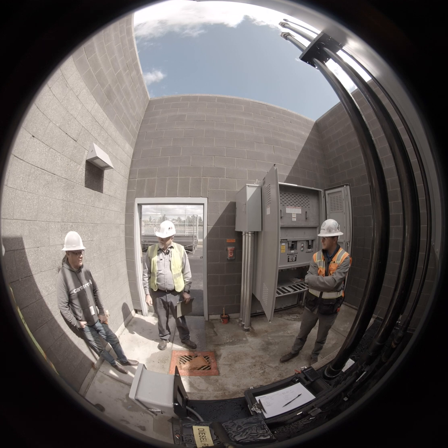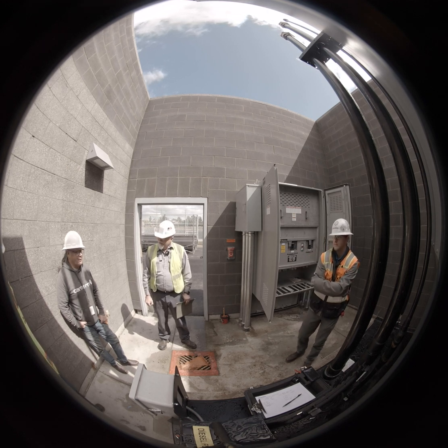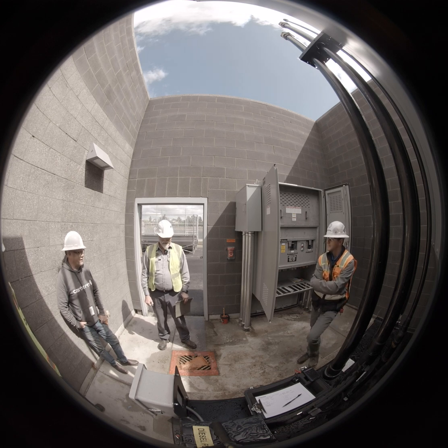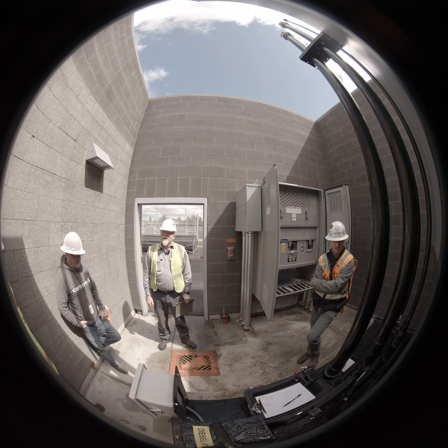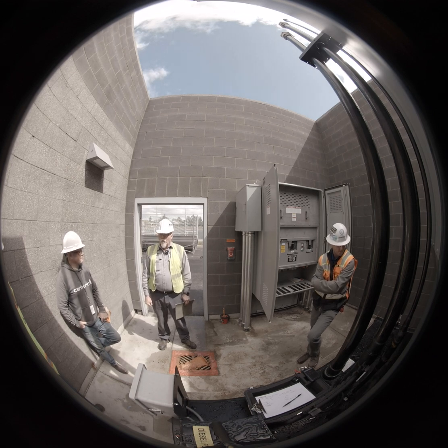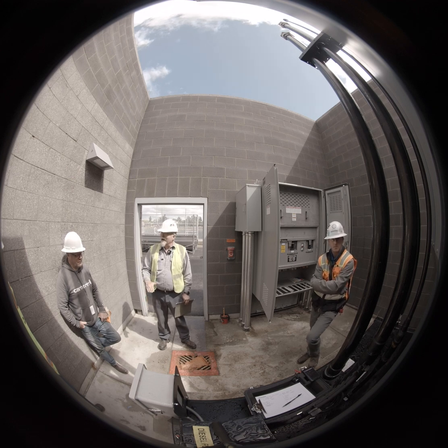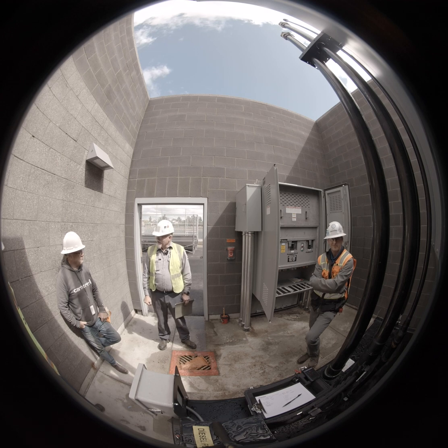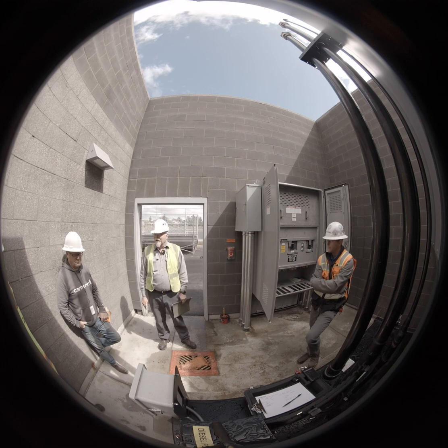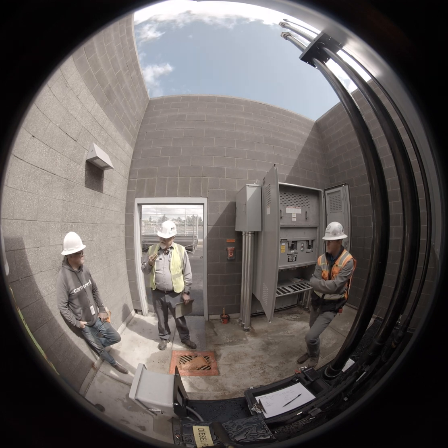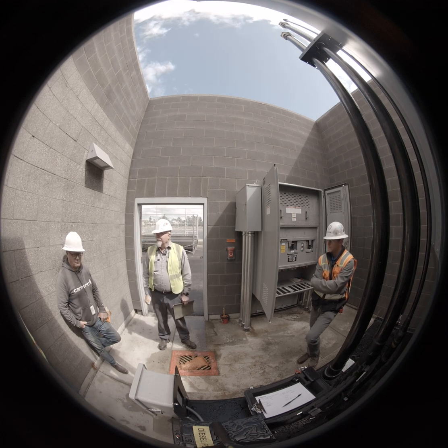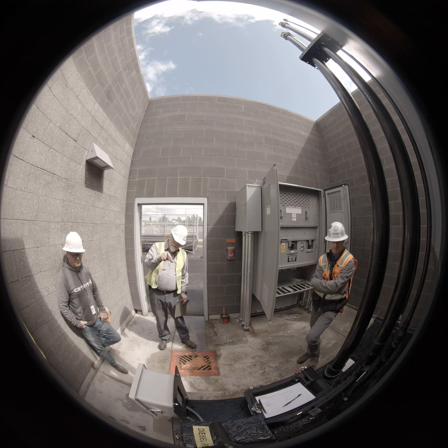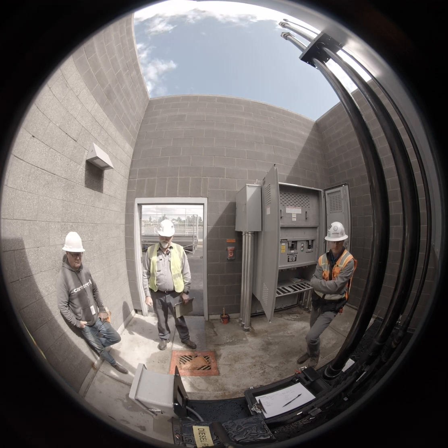I've had several of these filled that they come back with a high fuel line. Yes, that was my... They want to get as much in there as they can. That was my next comment. The overfuel limit on this will trigger an alarm. It can be silenced, but you cannot get rid of it until you burn the fuel back down. So 90% is a recommended maximum fuel on this tank. You have next to this alarm panel a fuel gauge for the vendor so that they can see how much fuel is in it. There's also another display on the control panel and another mechanical one down on the tank up inside, as we'll see in a little bit.